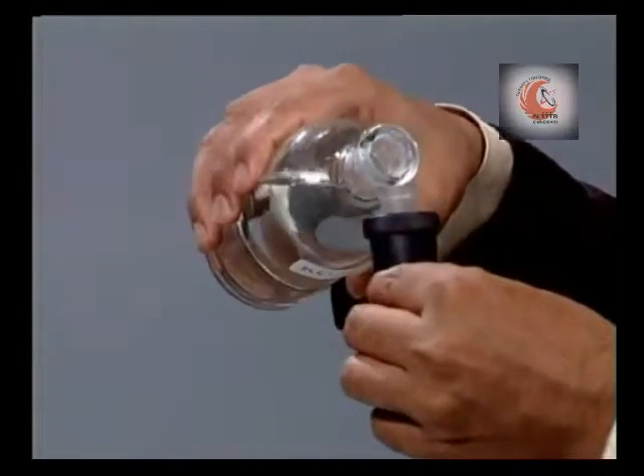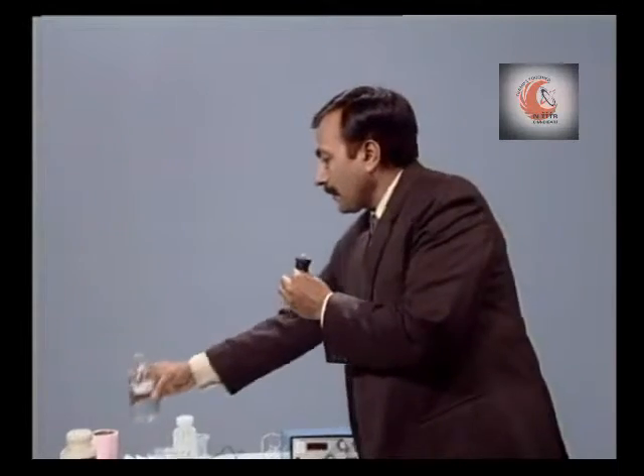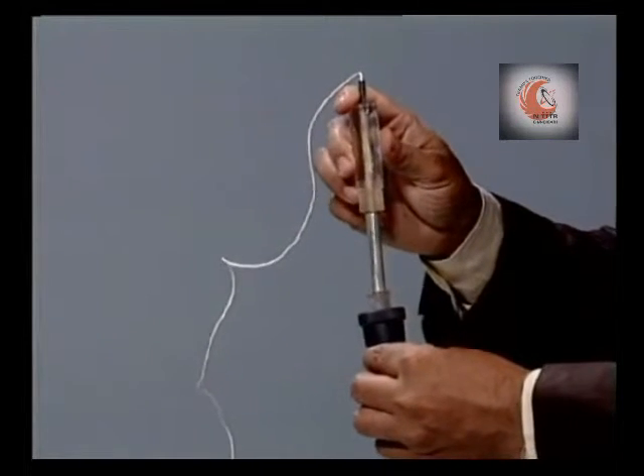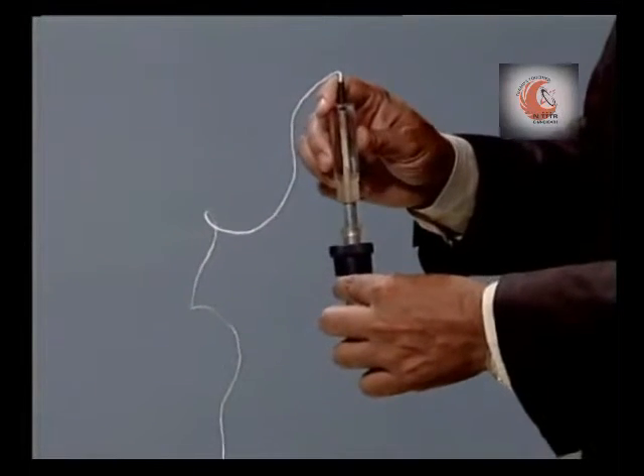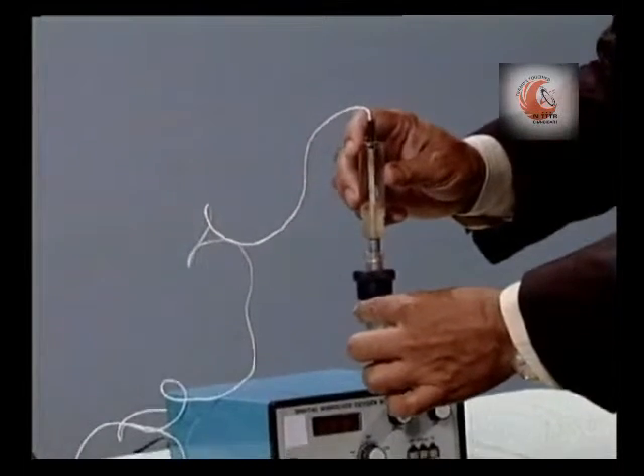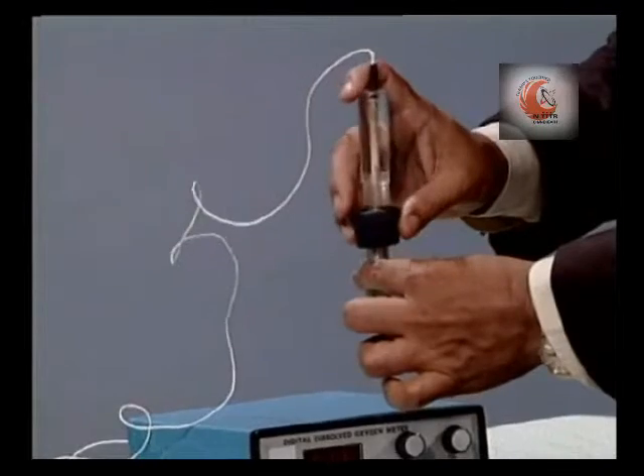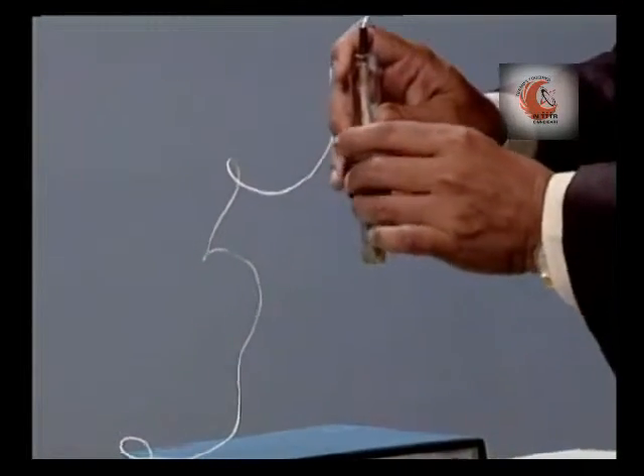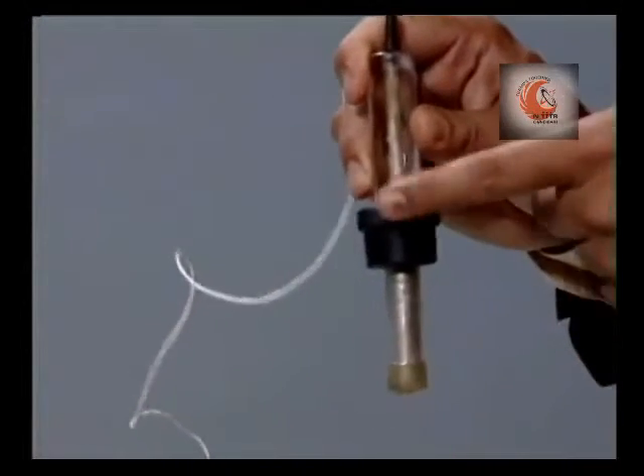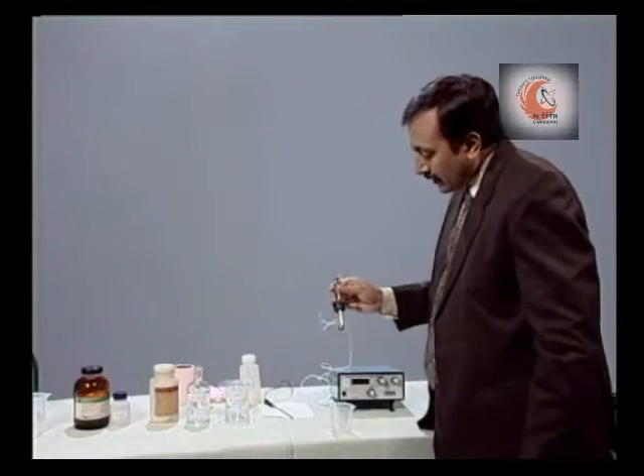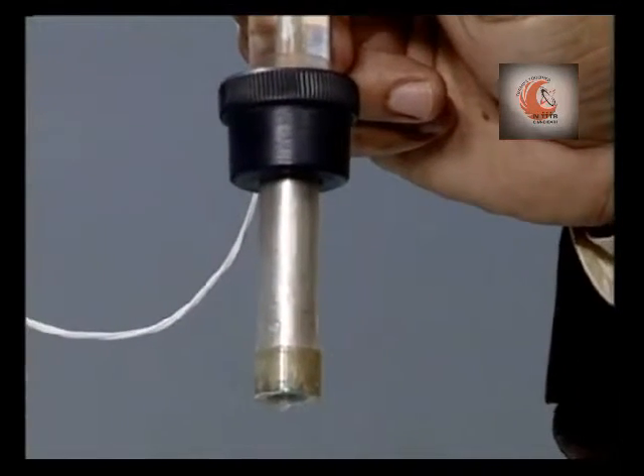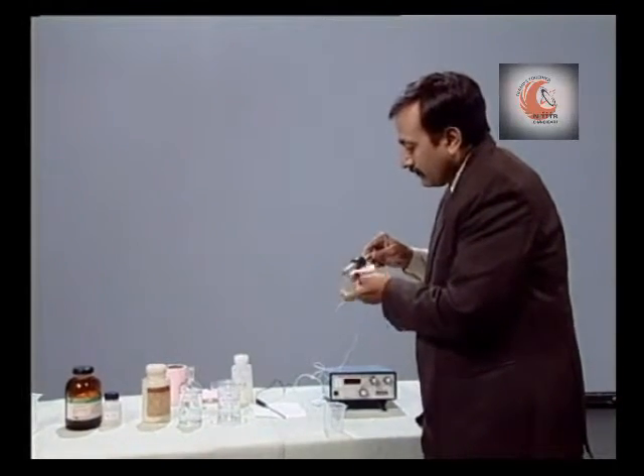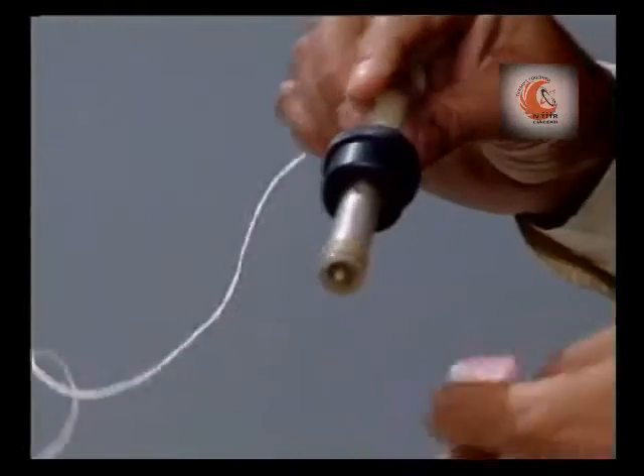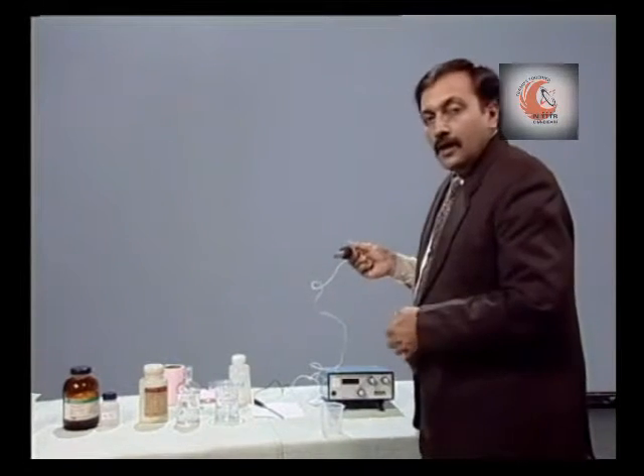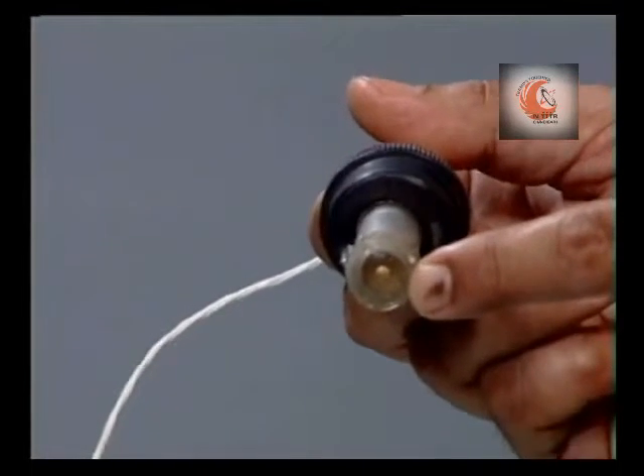Now pour some electrolyte and slowly insert the electrode. Now some electrolyte will overflow. Now close the cap. Check that there are no air bubbles inside. Now, in case this membrane is torn out, it has to be replaced with a new membrane.